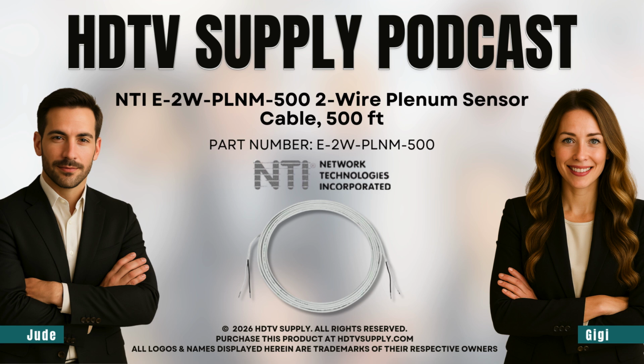So what is this actually connecting? The source sheet says it's for NTI's E2D, 5D, and 16D units. It connects what are called dry contact sensors, simple on or off states. Is a server room door open or closed? Is there water on the floor, yes or no? Simple binary information. This cable runs from those little sensors back to the NTI units, which act as the central brain of the system.